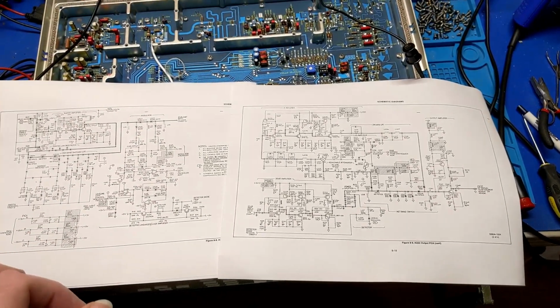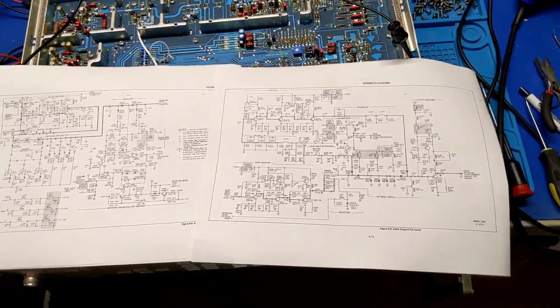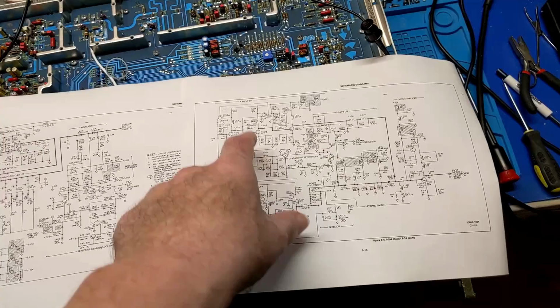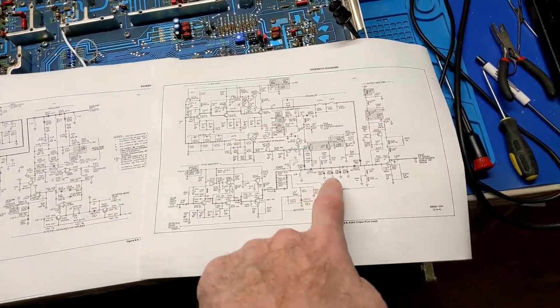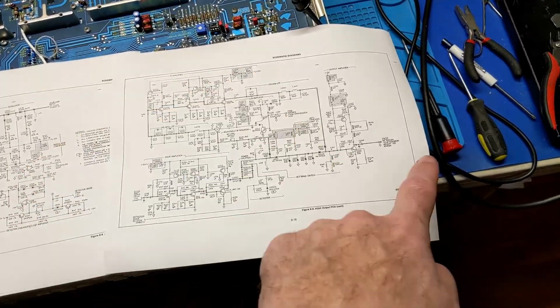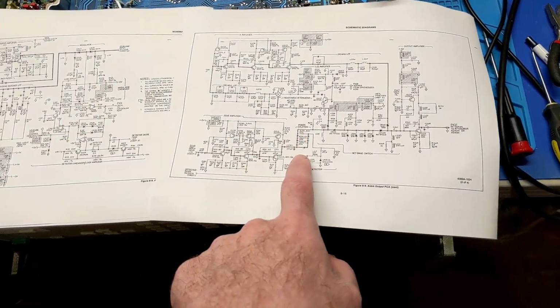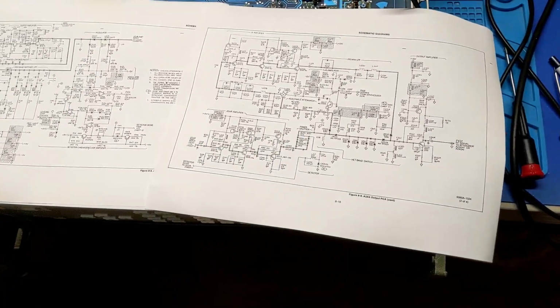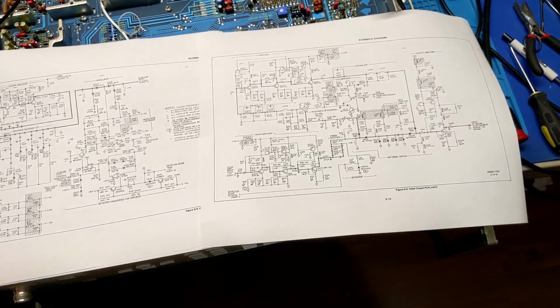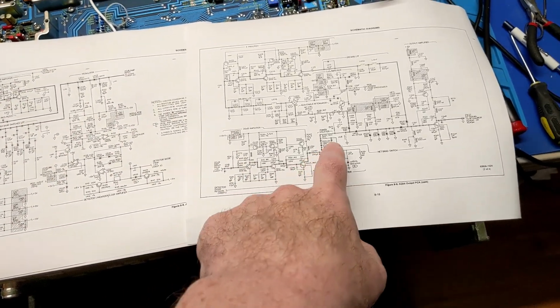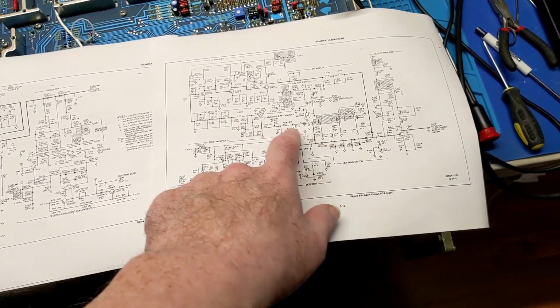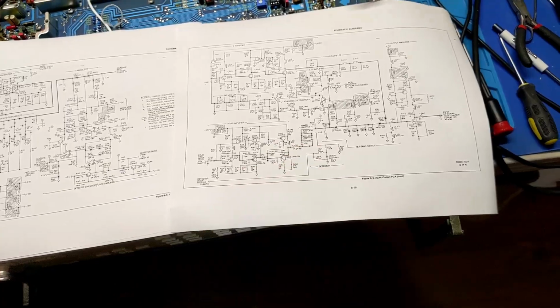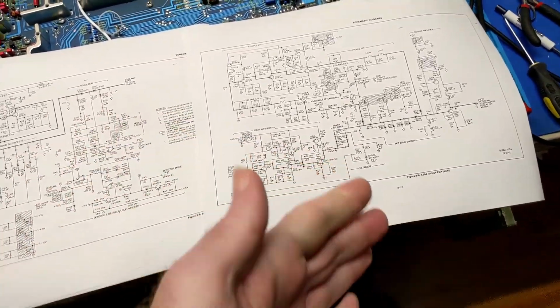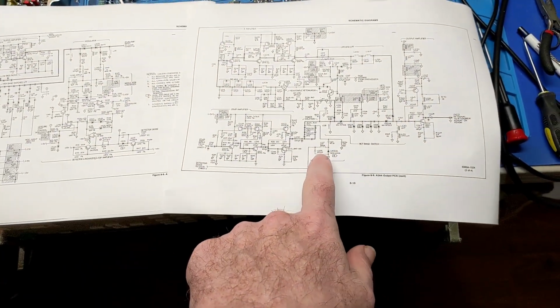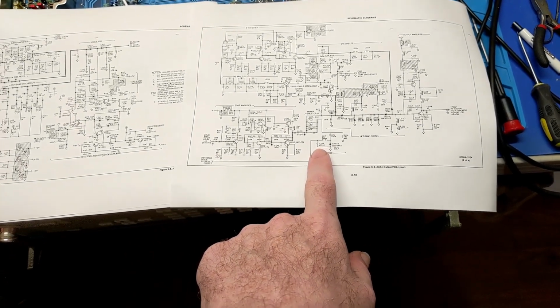So as we've seen several times now, when you go into low band, it kicks on the 15 volts to this circuit, so this circuit gets energized, and then it switches this network over so the RF goes through here instead of straight across. And that's when we see this signal fall flat on its face. So there's a couple of things that could be happening here. Either this amplifier is overloaded, so there's an RF short somewhere in here, either by the mixer or one of these passive networks, that's dragging this amplifier down to where the servo loop can't compensate, so it pegs to one side, the error response. And we saw that with monitoring this detector. It falls to almost zero when this thing goes to low band.